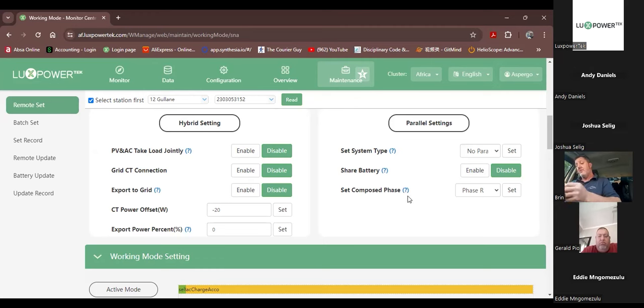And here, you can set the composed phase. Now, remember that the default setting is always phase R. But if you are going to go for a three-phase parallel, then first of all, the machines will auto-detect which phase they are connected to when you start up the grid, which is quite a cool feature. Or if you're working in an off-grid situation, in other words, you might be doing a three-phase installation on a farm, then you can go into each machine here. So here you will click on the drop down and you'll select the machine, and then here you will set the composed phase. So there's R, S, and T.